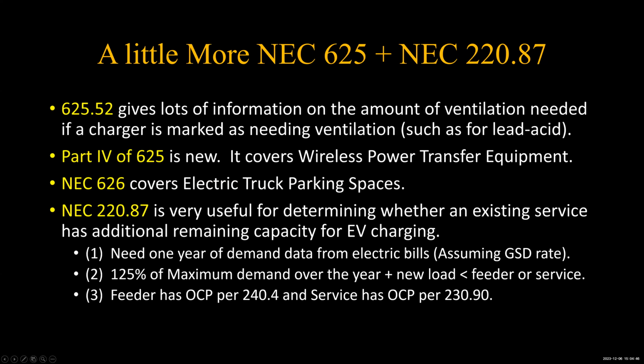But you need a year's worth of demand data, and most houses are not on general service demand, but guess what? Most commercial buildings are. So all you need is a copy of their last 12 months of electric bills, and take the highest demand, multiply it by 125%, and that's your new demand on that panel. Forget about what you calculated in terms of the first 10,000 watts at 100% and the remainder at 40%. You can do that. And what a surprise that sometimes turns out to be.